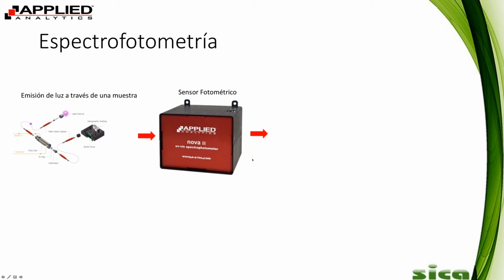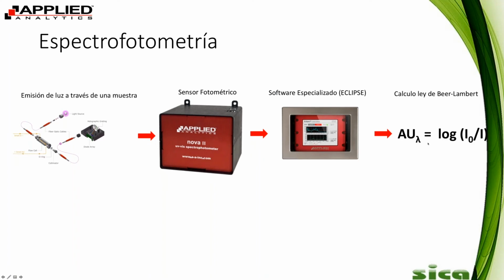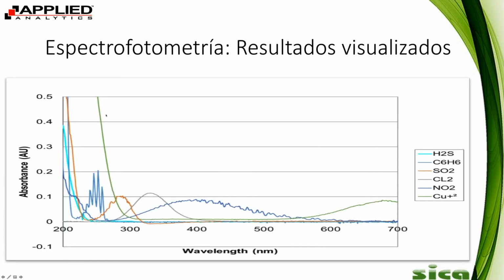So here you can see some different readings of what the spectrometer will show you. These are different outputs. With our analyzers, you can get numerical outputs, like a numerical chemical concentration. You can also get plots like this. And as you can see, every chemical has a very unique and very structured absorbance curve. Since they're all unique and pretty structured, we're able to observe the absorbance spectrum from a sample, and we're able to deconvolute, say, a total absorbance into speciated chemical absorbance spectrums.